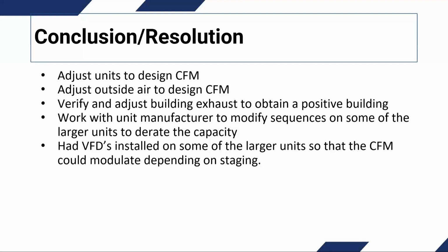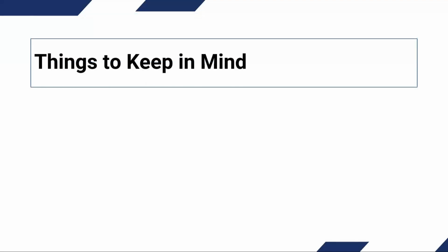On equipment now that we see with the digital scroll compressors and ECM motors, we see a lot of systems that are designed at way less than that to increase latent capacity. So once that was done, we had no problems with that building. The building worked fine. Again, we worked with the owner. The manufacturer was able to offer them some services as far as monitoring the system, and it's helped us in a long-term commitment with that particular client.